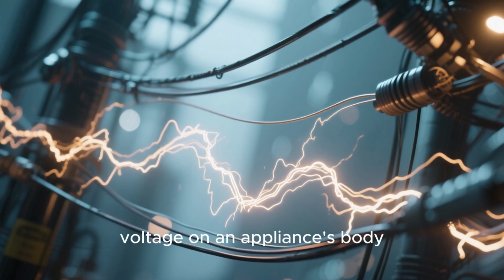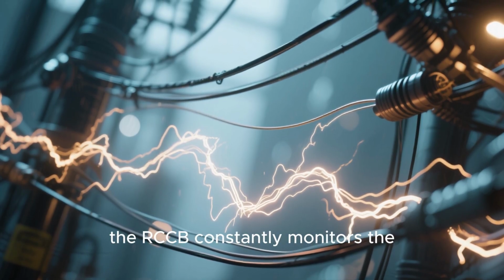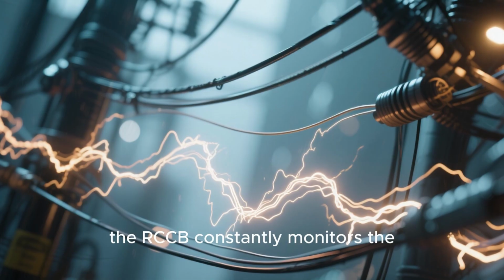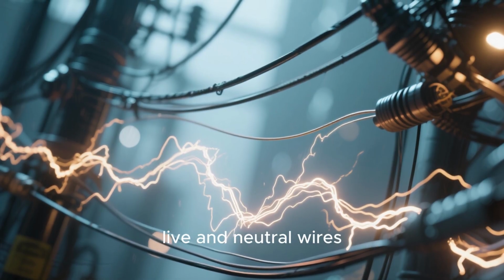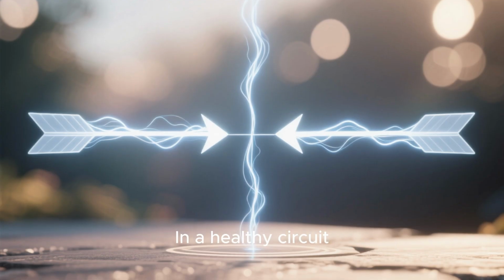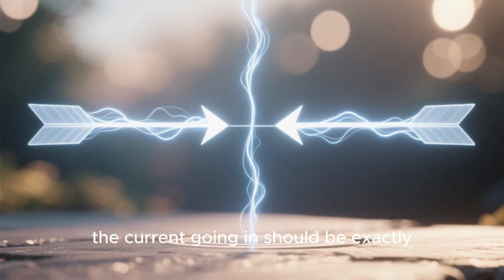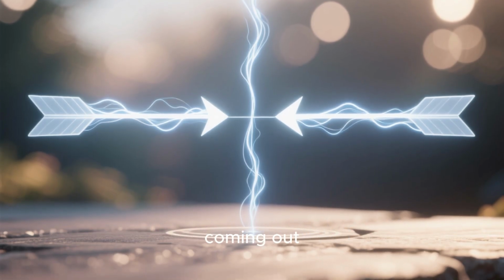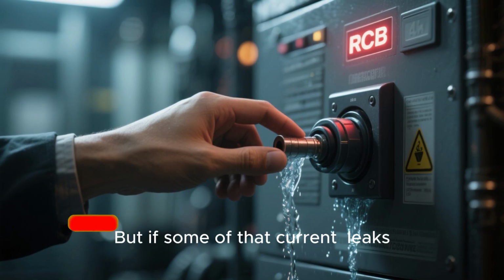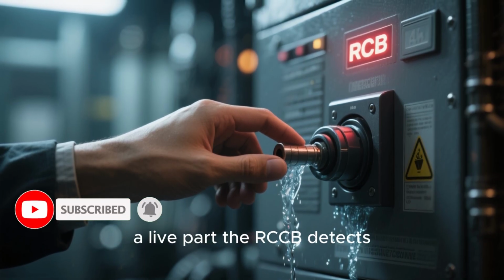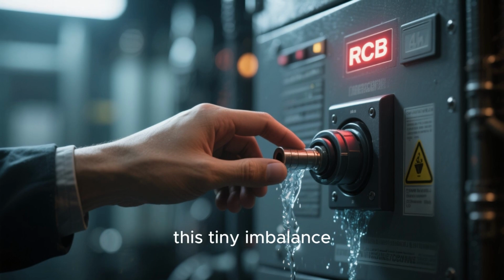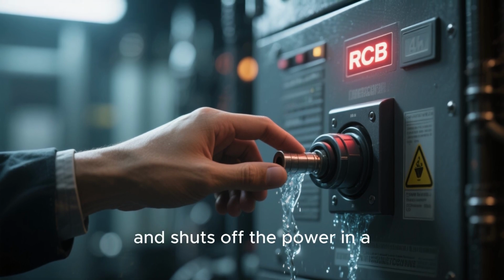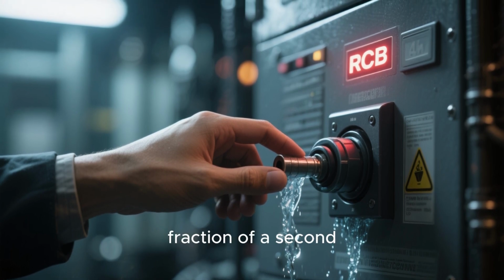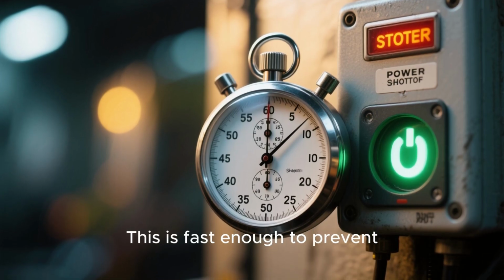Instead of looking for voltage on an appliance's body, the RCCB constantly monitors the balance of current flowing in the live and neutral wires. In a healthy circuit, the current going in should be exactly the same as the current coming out. But if some of that current leaks out, for example, through a person who has accidentally touched a live part, the RCCB detects this tiny imbalance and shuts off the power in a fraction of a second. This is fast enough to prevent serious injury or electrocution.